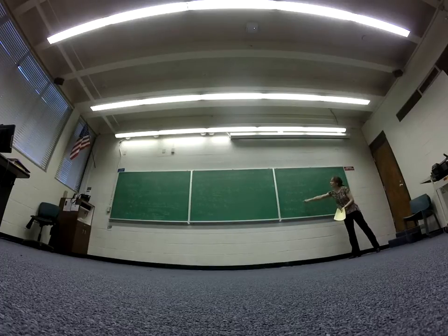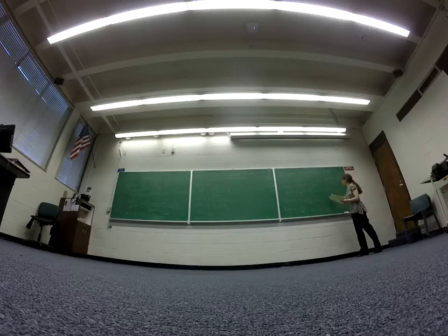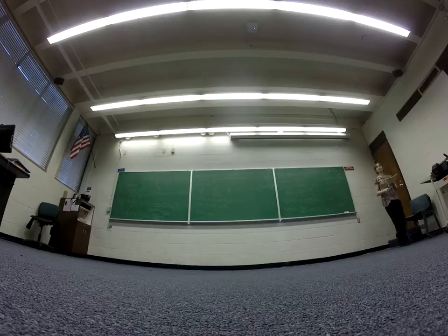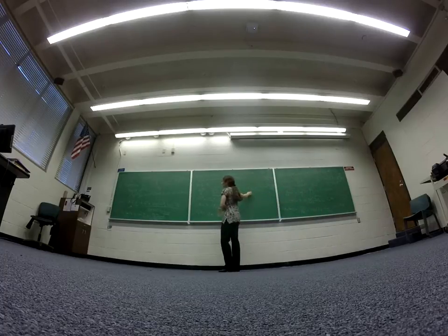If we put in our Reynolds number, 36,700, this number for the T, oh, oops, hold on, wait. This is the number for the T, sorry. The head loss for the pipe is actually much more than that. It is 11.76. Okay, sorry about that. Okay, that was the T. We're working over here.